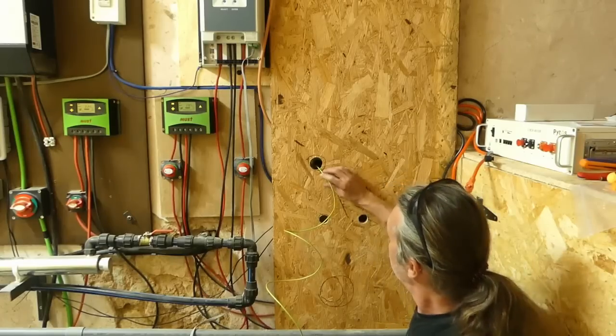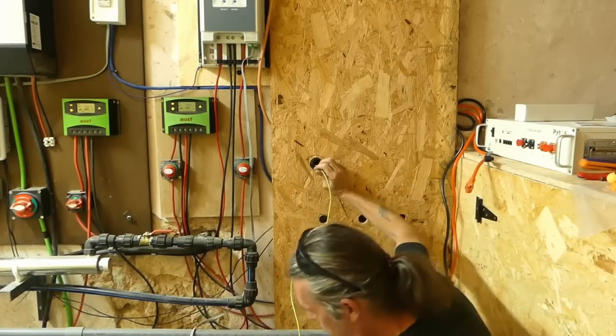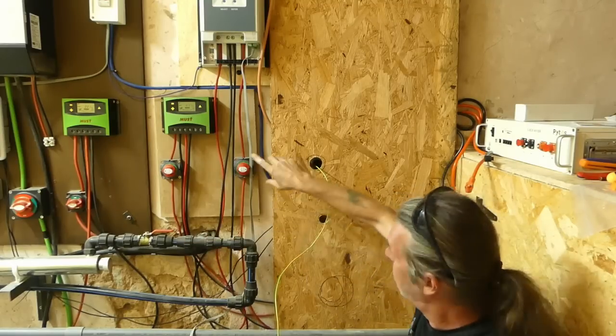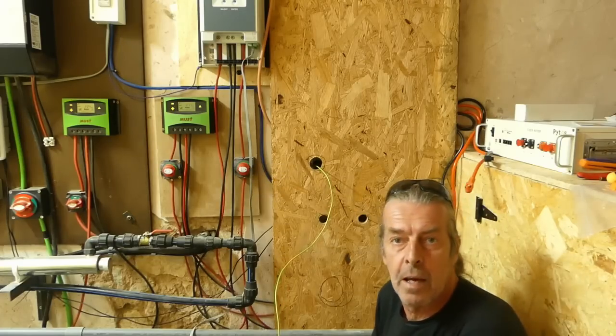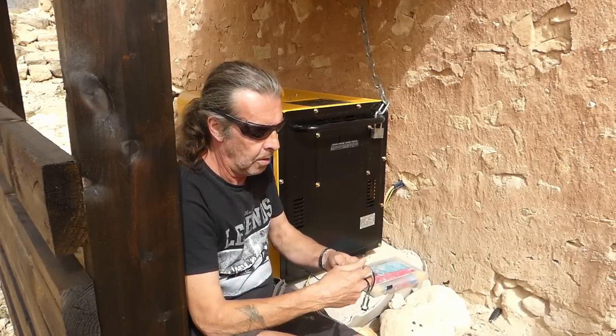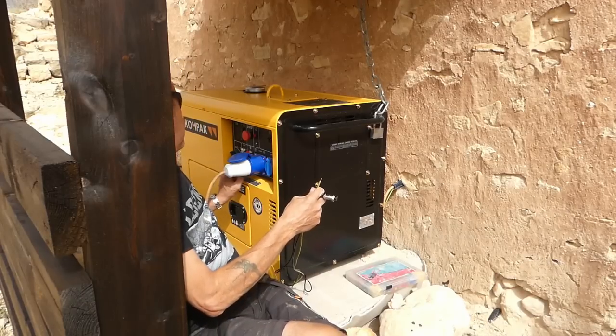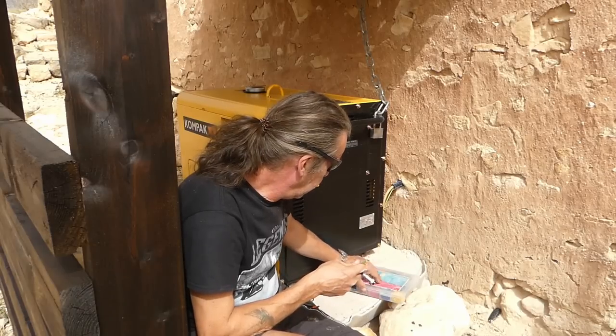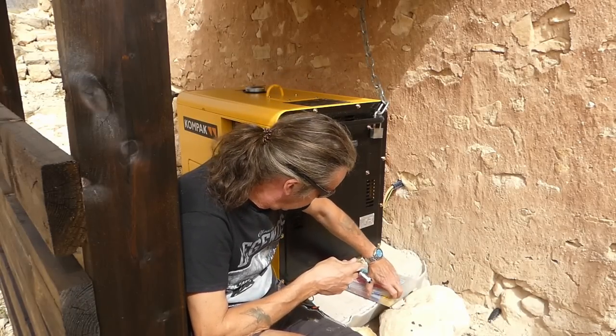The first thing I've done is fed my earth cable through to outside to the generator. I'm not cutting it off yet because I don't know where I'm going to put a junction box to tie them all together, but for now that'll do. So here they are - I'm going to take this up to my auto start wire. The auto start plug's in there and the earth goes right next to it. So I'm just going to put a connector on the end, just a crimp connector, and get him in place.